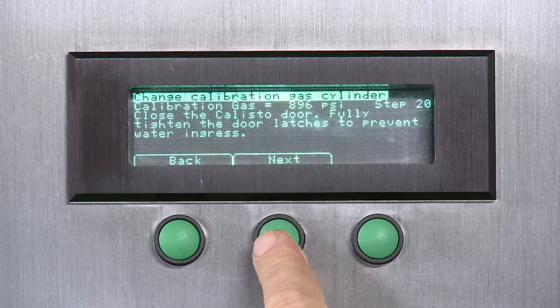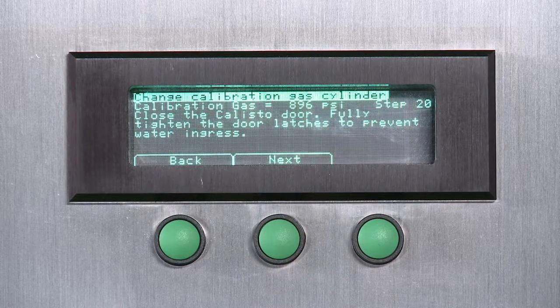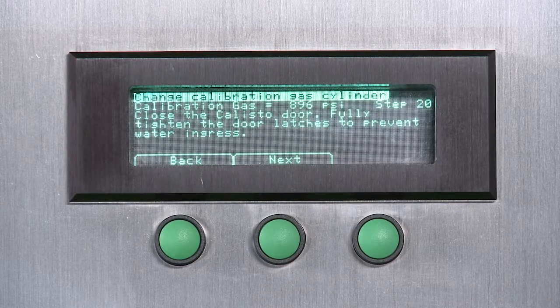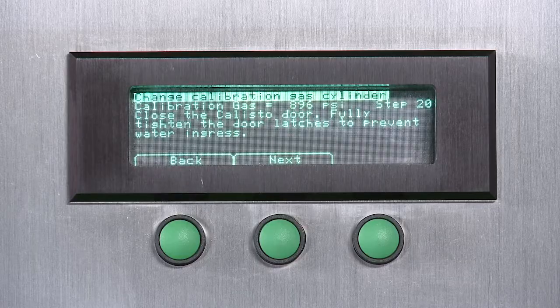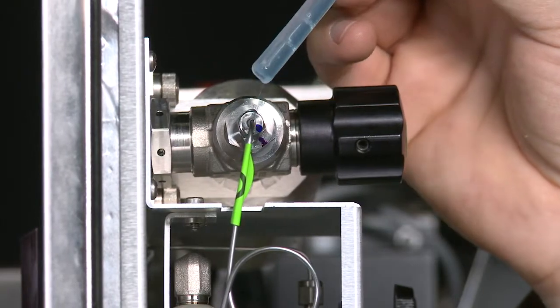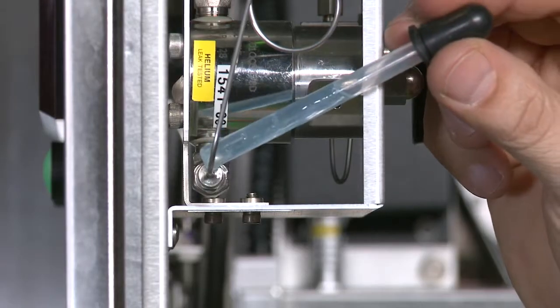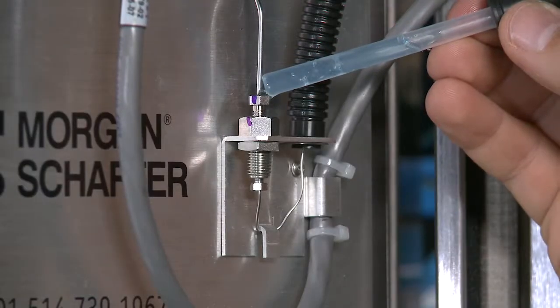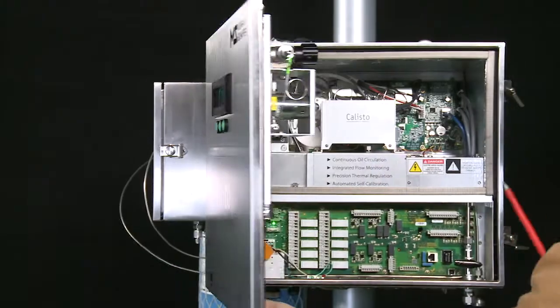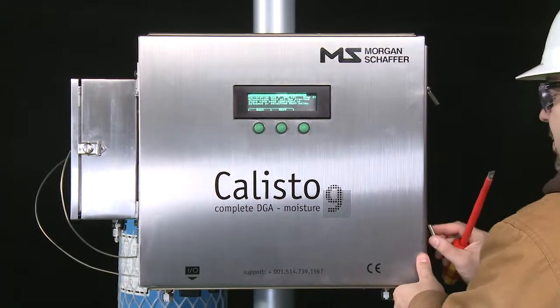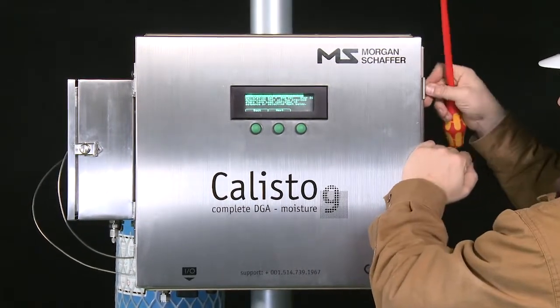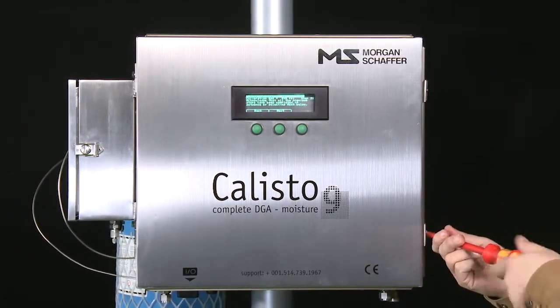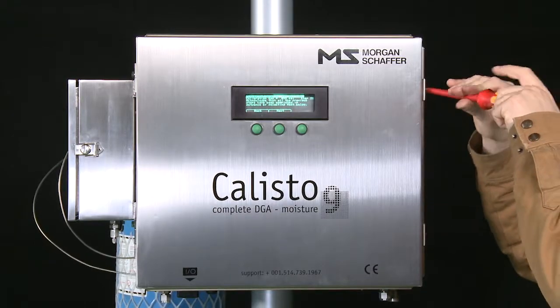Verify that the calibration gas pressure is at least 800 psi. If not, contact Morgan Schaffer. Use Snoop or helium detector to check that the cylinder connection is leak tight. Close the Calisto door. Fully tighten the door latches to prevent water ingress.